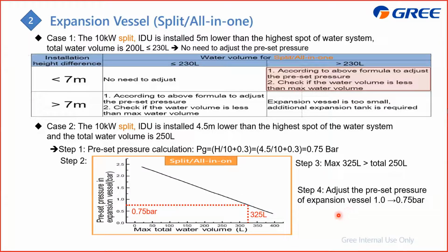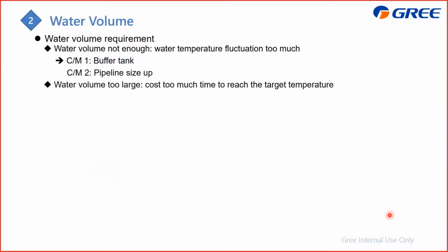And the last is just to adjust it. As for the water volume, you also know that if the water volume is too small, it will make the temperature fluctuate too much, which means the temperature is not stable. The countermeasure is first to use a buffer tank, and second to enlarge the pipeline. And if the water volume inside the water system is too large, it will cost the system too much power to heat up the water, which means the customer will feel that it is not cold or not cool, and they will have to wait too long.